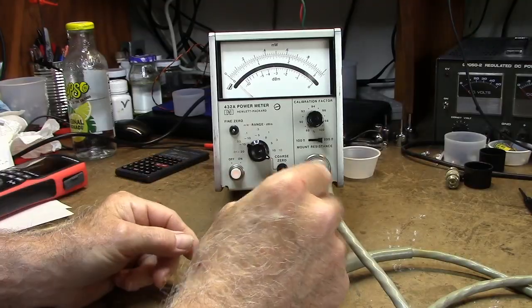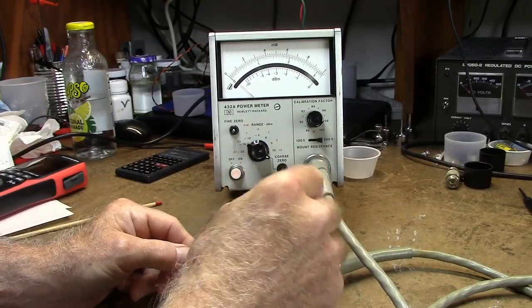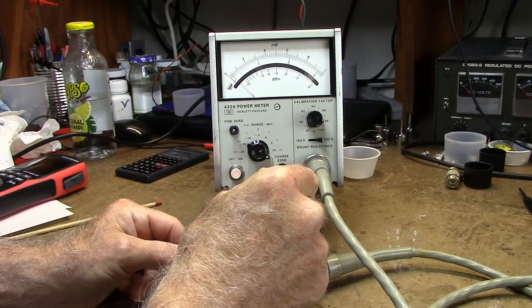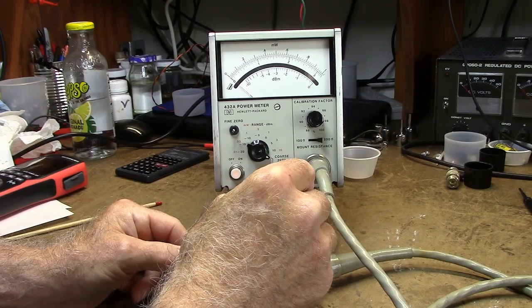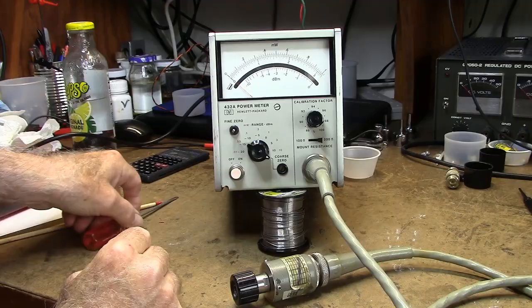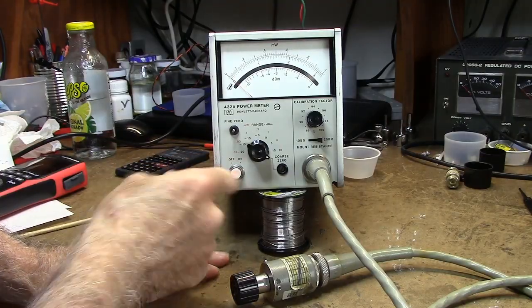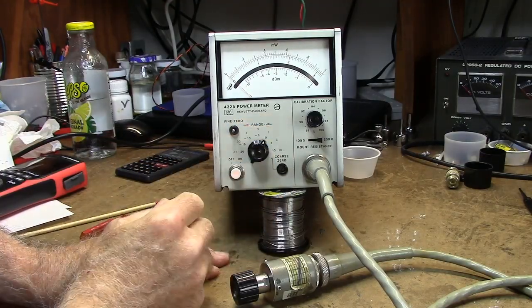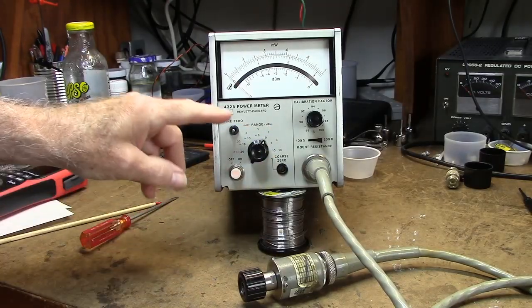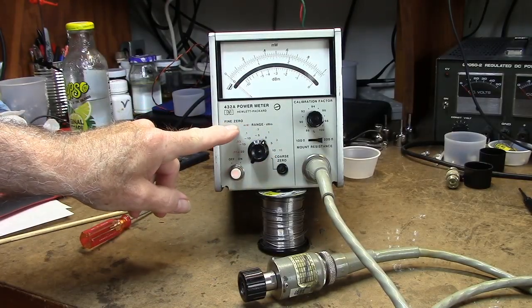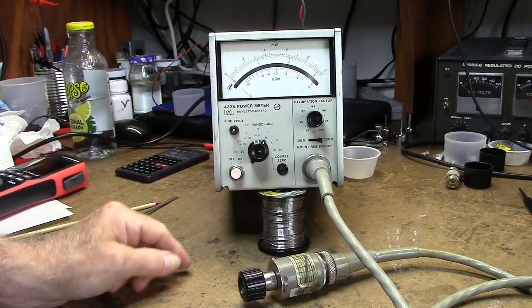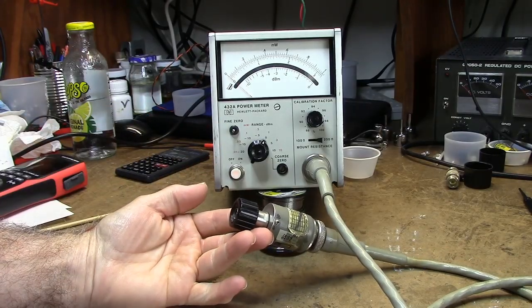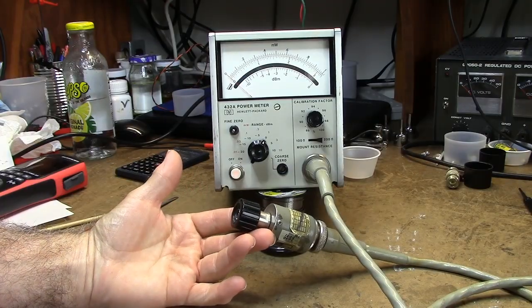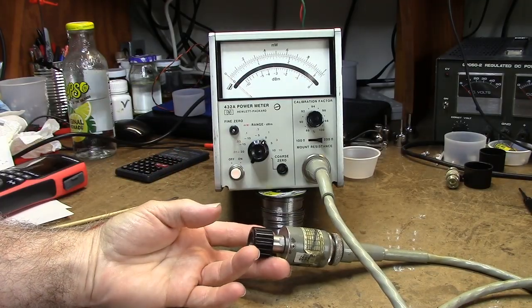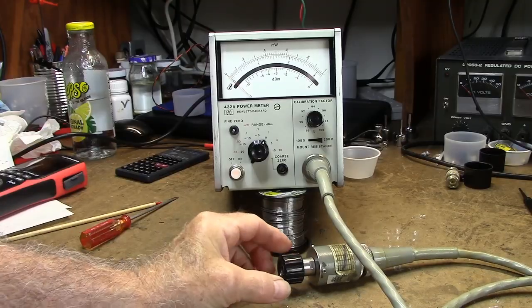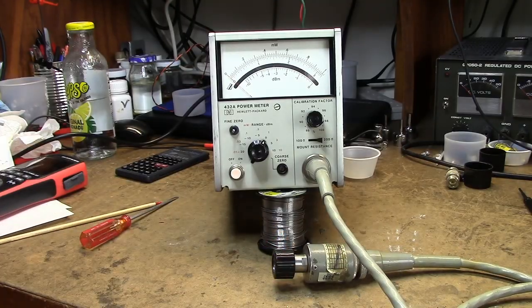It's jumping around a little bit. It hasn't been used in a while. It may be a little dirty here, so let's exercise it. That looks pretty close. And then according to the instructions, you set your range switch to wherever you want it, and then there's a fine 0 that you push, and this zeroes out your fine 0 here. So now it should be ready to take a measurement. Hopefully we'll get something coming in here. I'm probably going to use this on transmitters. Of course, you can't connect this up directly. You'd blow the transmitters up.